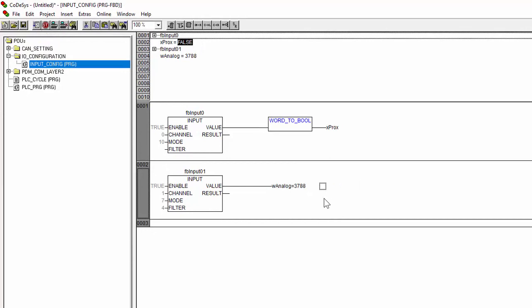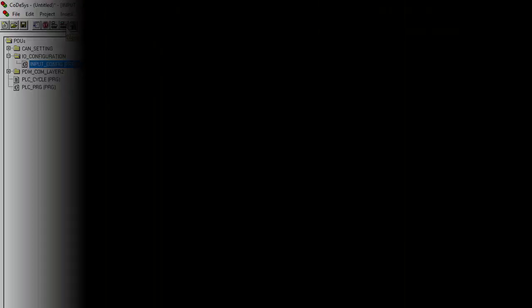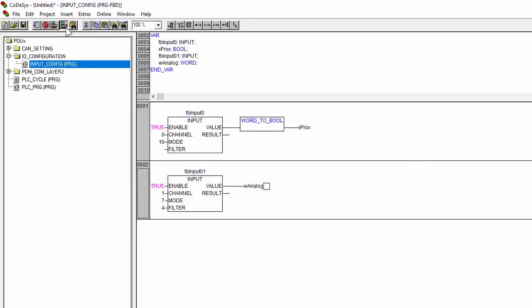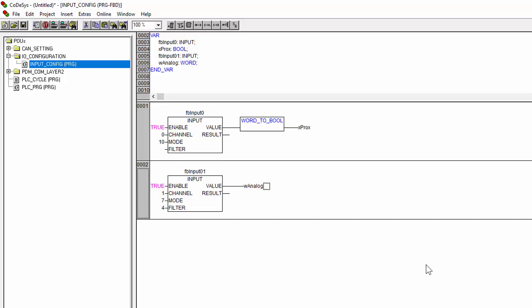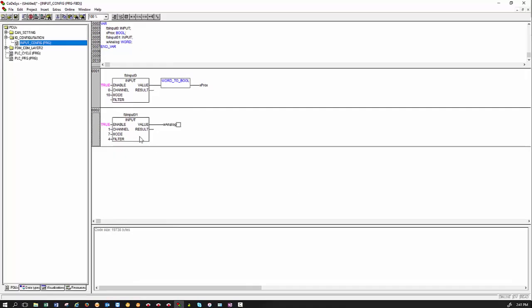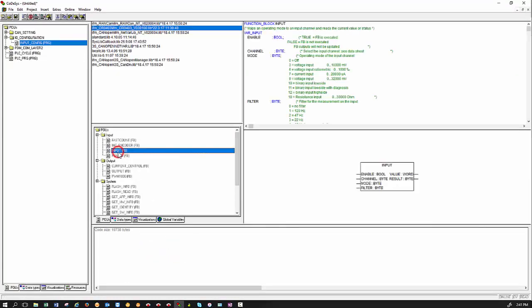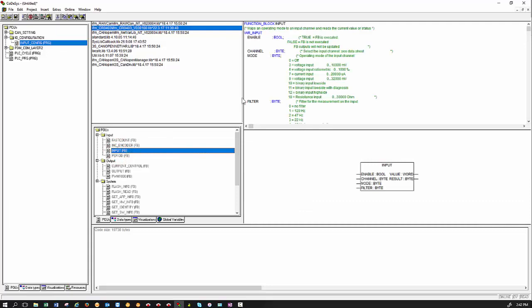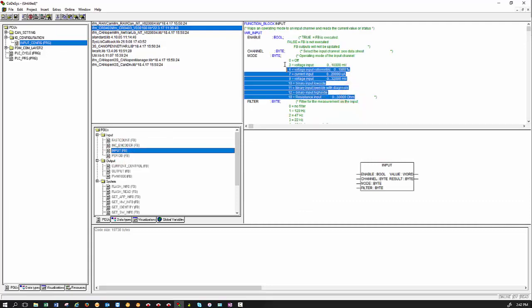So you can already see on an analog channel, we are getting roughly 4 milliamps because it's a 4 to 20 milliamps sensor that I have connected. So if I now change the value so you can see the value go up to 20 milliamps. So the value that you see here is in microamps. So it goes from 4000 microamps to 20,000 microamps. Now in order to show you now the digital input, you will see that now if I, you can see the prox turning on and off. So this way you can configure your input to be digital, analog or resistance. So you just need to look in the library manager on the input function block what modes it can be, what modes can be used essentially to configure those input channels.